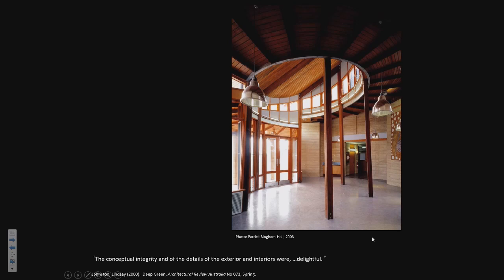So in this building we learnt that the thermal tank had a shoulder period where it had to switch from hot to cold, with no additional capacity. So we put 2 tanks in this building, one cold and one hot, for these shoulder seasons. That was also important because when you get 200 plus people filling this lecture theatre, that's a lot of hot, warm bodies, and you need some instant cooling even though you might have been in winter mode.